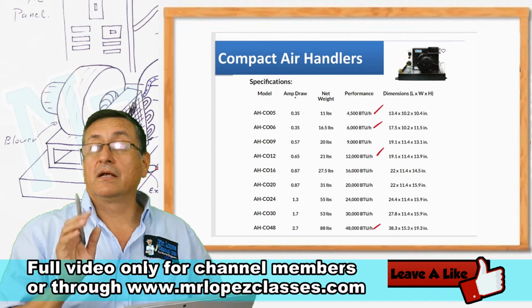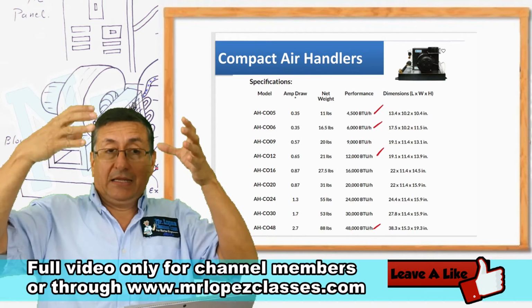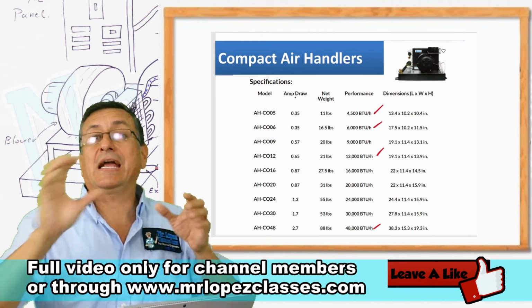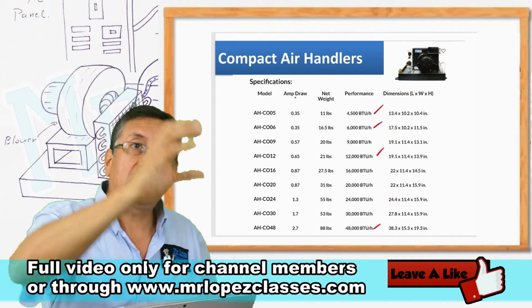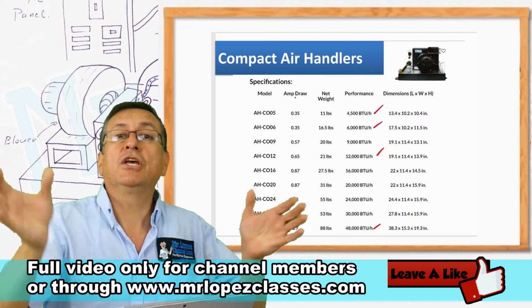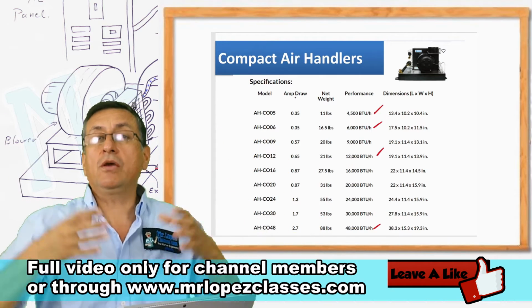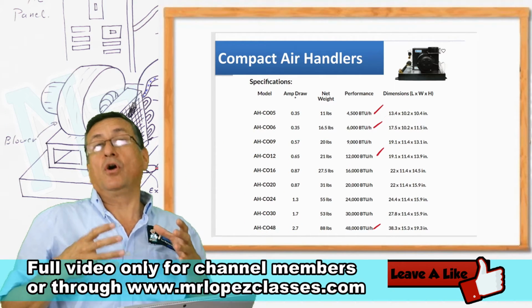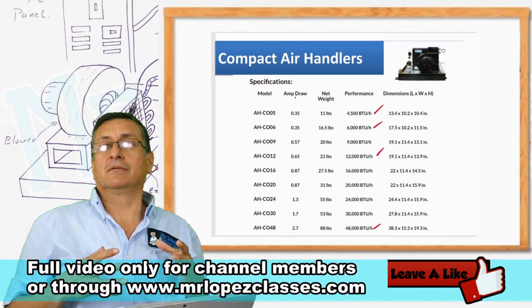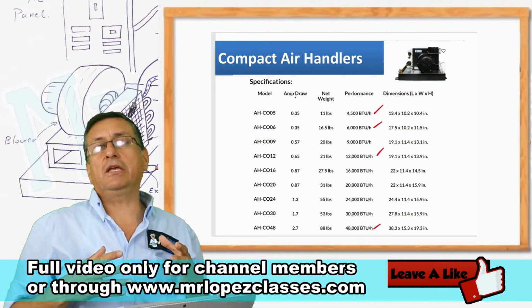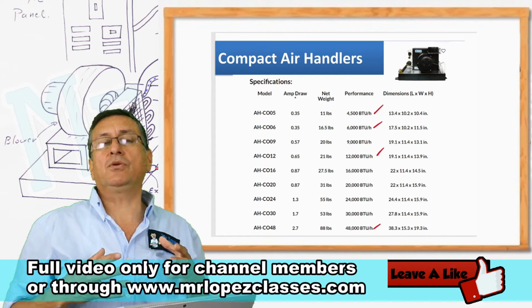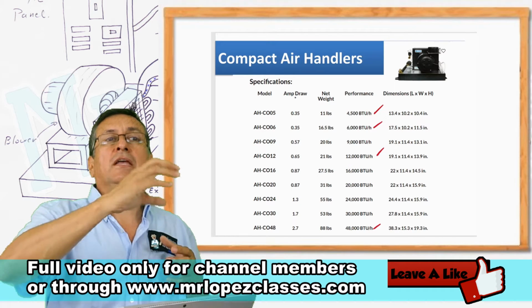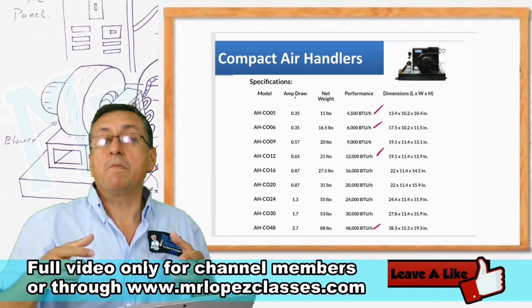Remember that the capacity of the air handlers, this plus this plus this plus this, all of them together should be equal to the capacity of the central unit. The central unit is 60,000 BTUs. I can divide it into different air handlers.